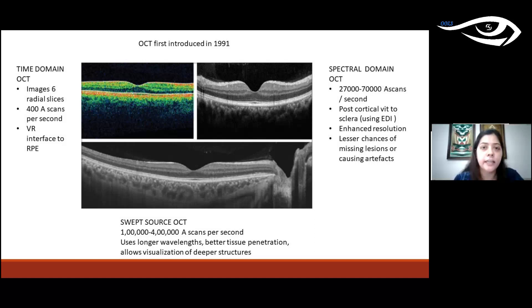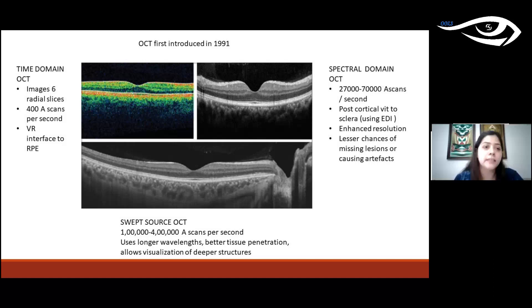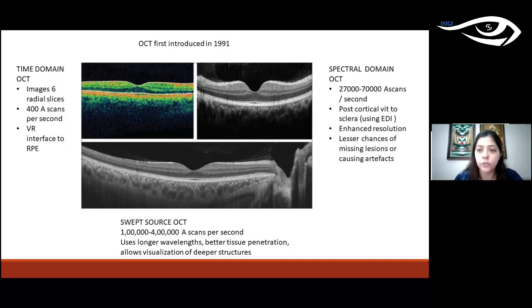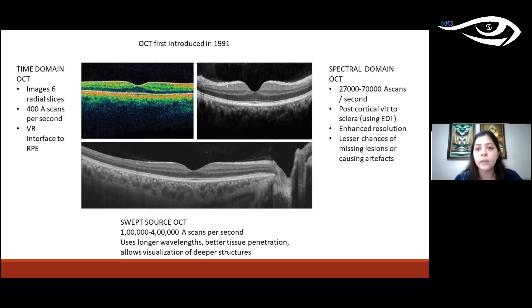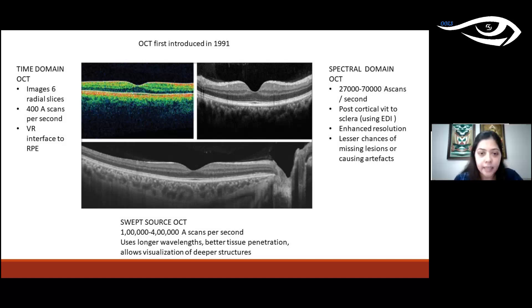OCT was first introduced in 1991 and has undergone significant technological change. Initially we had time domain OCT taking about 400 A-scans per second. This moved on to spectral domain OCT, which captures up to 70,000 A-scans per second, giving very high resolution and fewer artifacts. Spectral domain OCT also features enhanced depth imaging (EDI), allowing visualization up to the sclera. The newest technology is swept source OCT, with 100,000 to 400,000 A-scans per second, using longer wavelengths for better tissue penetration and deeper structure visualization.